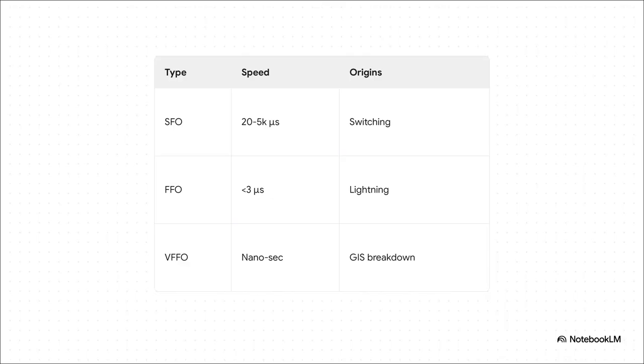And this brilliantly illustrates the complete spectrum of the threats we've just discussed. There is an inverse relationship at play here. As the event duration shrinks from thousands of microseconds down to mere nanoseconds, the rate of rise sharpens, and the specialized stress on the grid's insulation materials becomes increasingly extreme. Understanding the breakdown on this table is absolutely fundamental for proper insulation coordination.